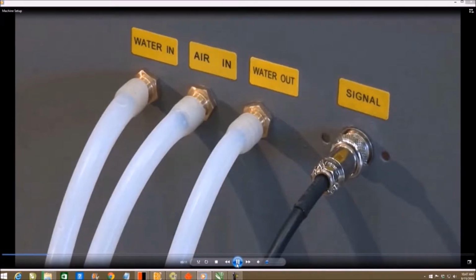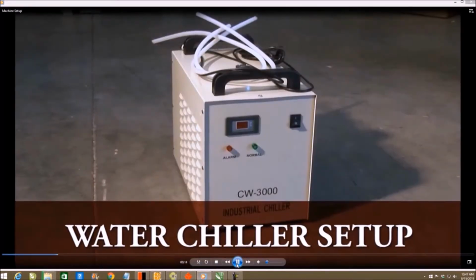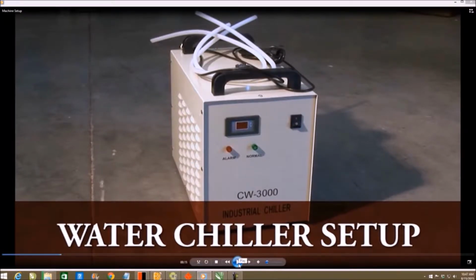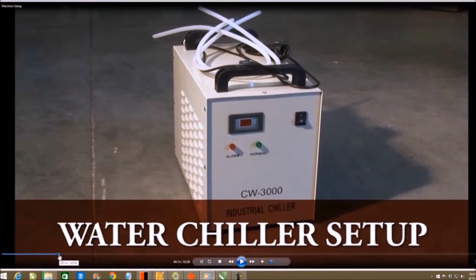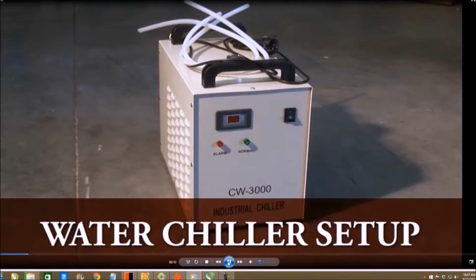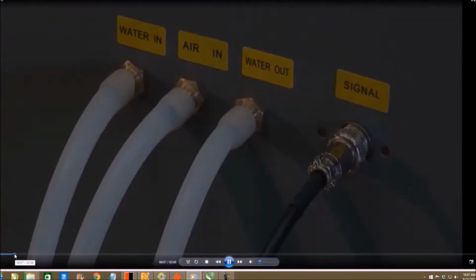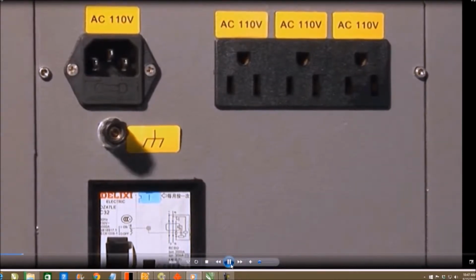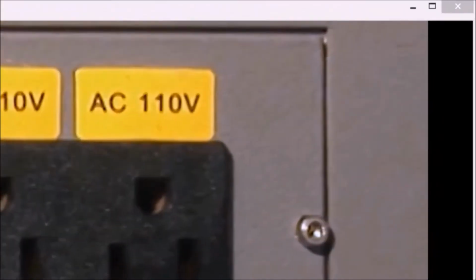But as we move forward here in it, you're going to see the water chiller. This is very important. You only put distilled water in it. But on the back end of the unit there, set up the chiller, as I slide even further back, right there, ground. Make sure you put a ground onto the back of your unit. If you have a lightning strike, it will save your laser. All right, that's very important.